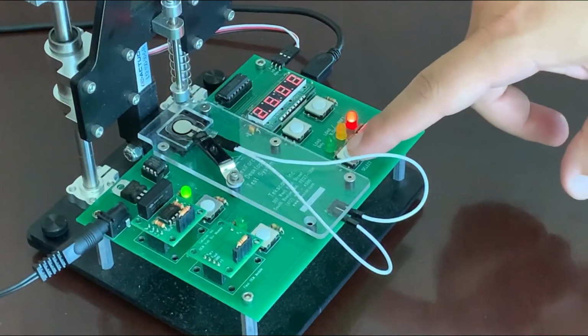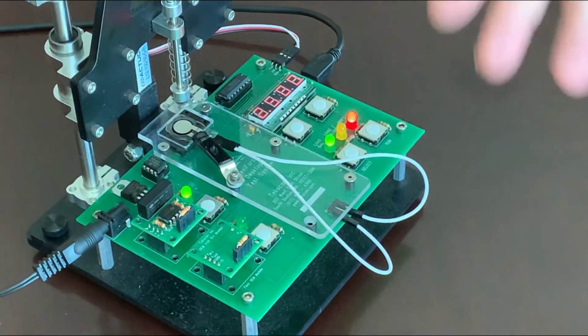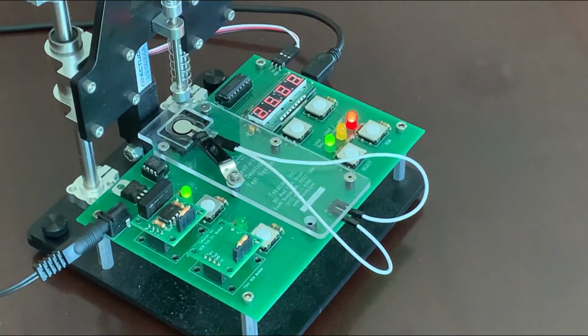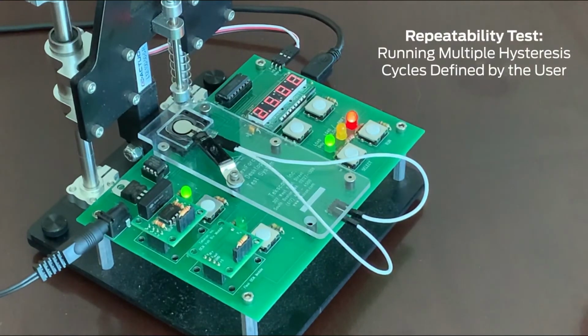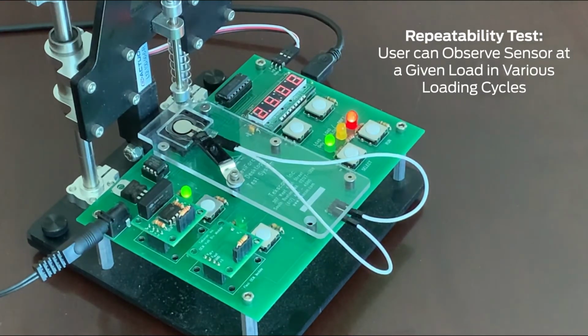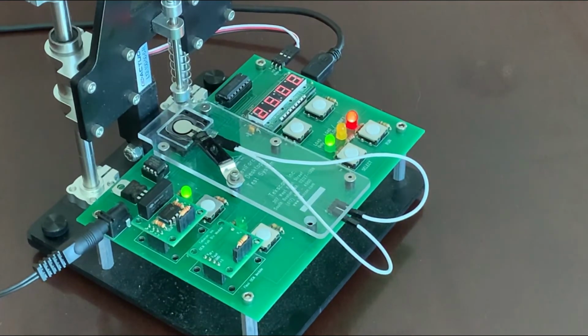We'll hit the select button one more time. As you can see, the green and red LEDs are both lit, indicating that the repeatability test profile has been selected. What the repeatability test profile is going to do is run the hysteresis load-unload profile multiple times at a user-defined number of cycles. This will allow you to observe the sensor's output at a given load in various loading cycles, so that you can determine the sensor's repeatability.